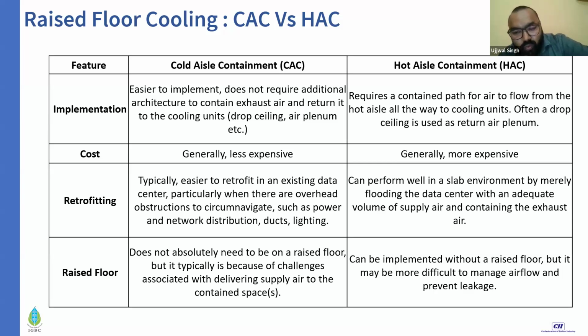Now, in what sense is hot aisle containment more preferable? If you ask me personally, if budget is not a challenge, my personal favorite is hot aisle containment. The major reason, the major pro of having hot aisle containment, is that your whole data center is filled up with chilled air at whatever supply air temperature you have in your data center.